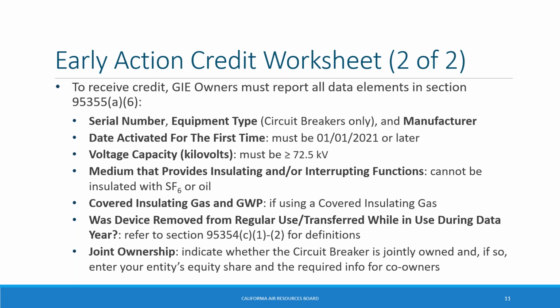Voltage capacity must also be reported. Only circuit breakers with a voltage capacity of 72.5 kV or greater are eligible for credit. The medium that provides insulating and/or interrupting function must also be reported and cannot be SF6 or oil. If your non-SF6 circuit breaker uses a covered insulating gas as defined in the regulation, report the name of the gas and its global warming potential, also known as GWP.